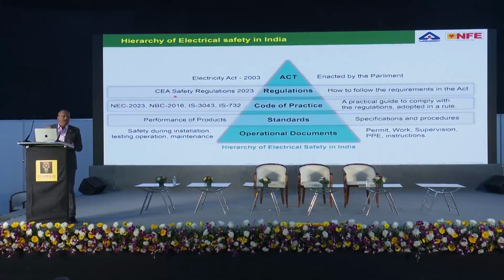Now, a regulation will contain subjects related to generation, transmission, distribution, and so many things. Majority, the regulation talks about the safety up to the point of commencement of supply. That means generation, transmission, up to the meter board. Inside the meter board, or within the consumer premise, we have to follow the code of practices such as NEC, NBC, and so on.